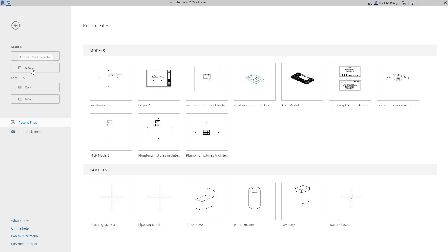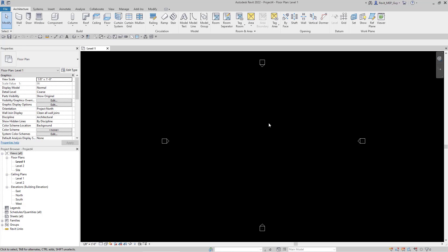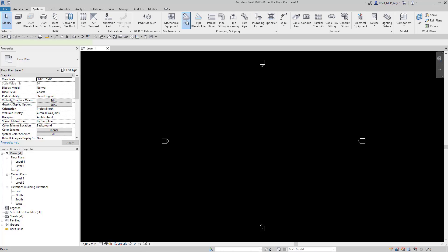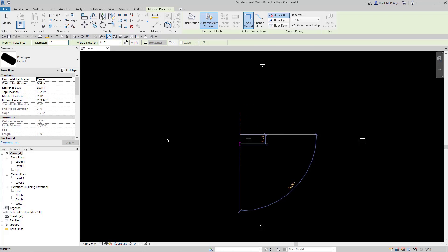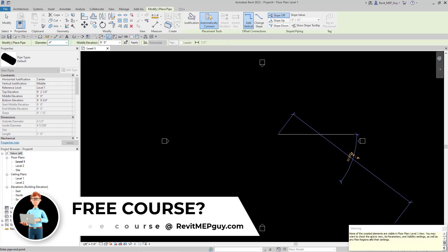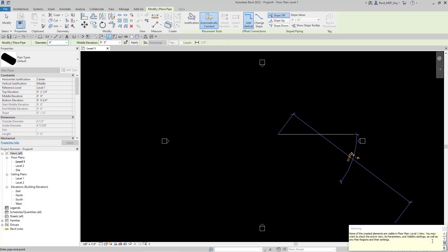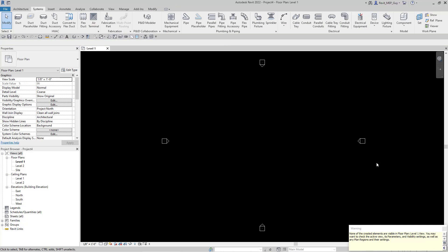The first thing you're going to want to do is open up a new project. I'm going to show you what happens if we open up an architectural template file. Revit loads a certain amount of families depending on whatever template you are using. So if we go to Systems and we go to Pipe in an architectural template and start to draw the pipe, you'll see that nothing's happening. And when I finish drawing the pipe, we get a warning that says none of the created elements are visible in floor plan. Essentially what that's saying is something is wrong in this view and it's not allowing you to see the pipe.